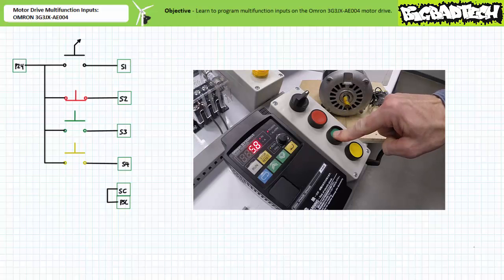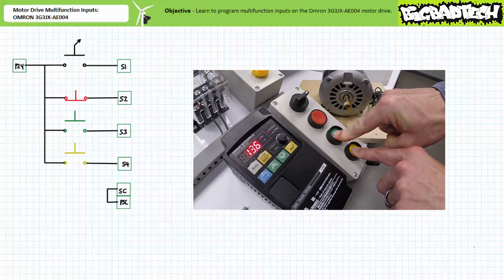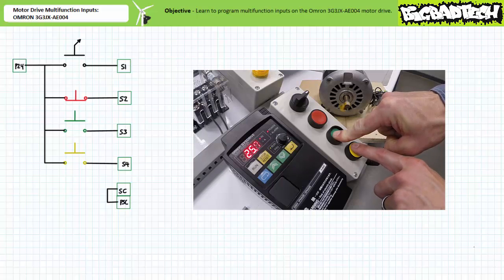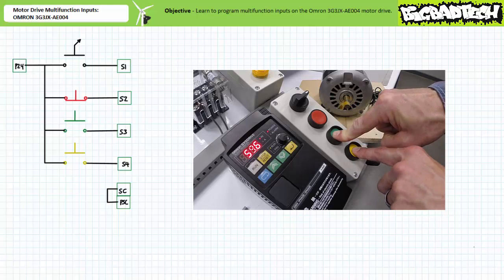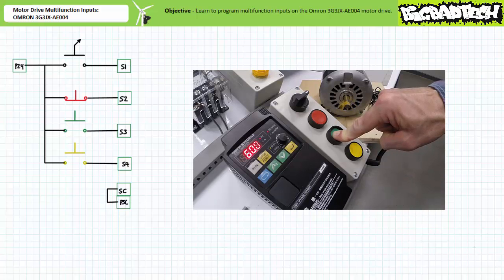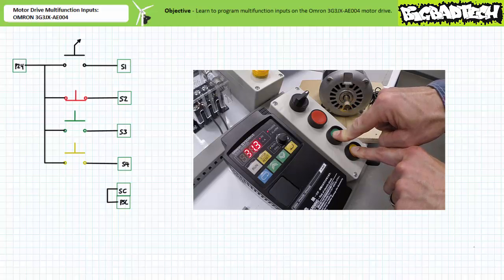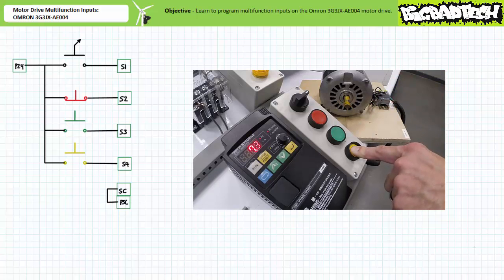When the forward input closes and is held closed, the motor drive accelerates the motor as previously. When the reverse input also closes, the motor drive doesn't burst into a ball of white hot fire, but rather begins a temporary deceleration whenever both inputs are being held closed. When given enough time to complete acceleration in the forward direction, the momentary closure of the reversing input also temporarily decelerates the motor whenever both inputs are being held closed. When both inputs are held closed long enough to fully decelerate the motor, the motor drive keeps the motor at rest until only one input is clearly asserted. When reverse remains closed and forward opens, the motor drive accelerates the motor in the opposite direction.